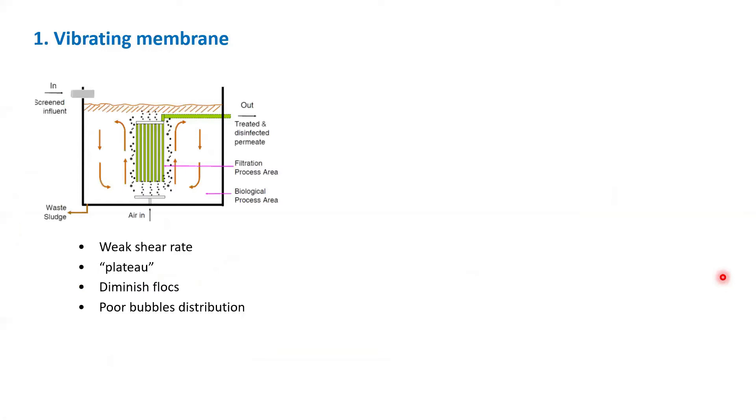The first approach is using vibrating membranes. This is part of my old study. Currently, people use coarse bubble aeration. When you use the aeration to scour off fouling, it has a few inherent limitations. Air bubble only produces weak shear rate. It reaches plateau, which means at one point you cannot improve the permeability. By pumping air, you achieve sort of cleanings, but at one point you cannot clean anymore. In the context of MBRs, it might also alter the feed condition, making it fouling prone. And then you have problem with bubble distribution.